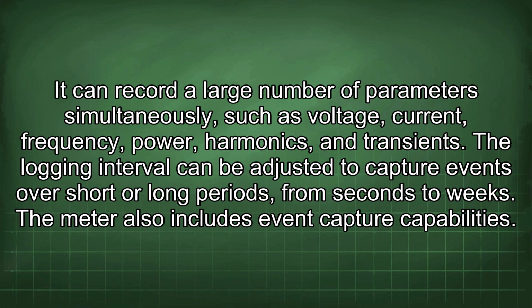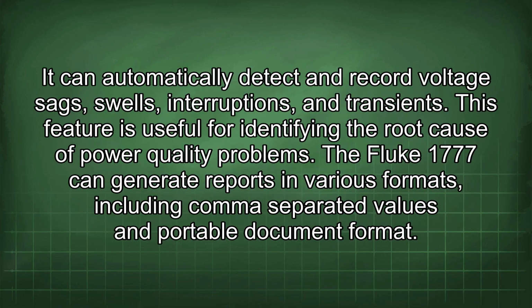The meter also includes event capture capabilities. It can automatically detect and record voltage sags, swells, interruptions, and transients. This feature is useful for identifying the root cause of power quality problems.